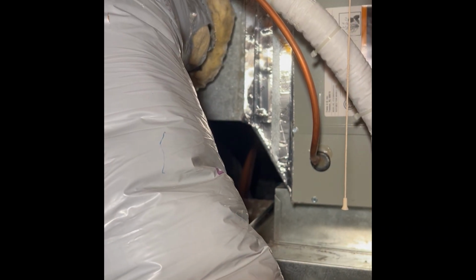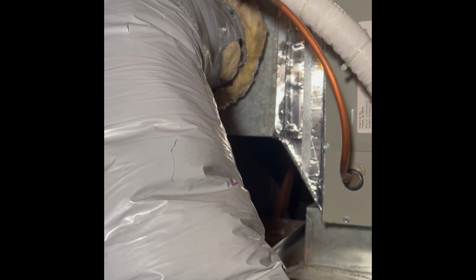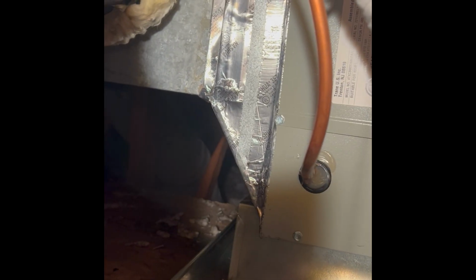So this furnace is designed to produce, I don't know what this one is, let's say 60,000 BTUs of heat. It needs 1200 CFM of air to blow across the heat exchanger, releasing that heat out into the house. And it's not able to do that, so it just gets hotter and hotter because it doesn't have enough airflow. The reason it doesn't have enough airflow is, if you look at the size of this coil, they attached it to a plenum that's too small, and that's not enough transition. Also, when I counted up the duct runs, there's not enough of them, so it can't release the heat because the ductwork's too small.